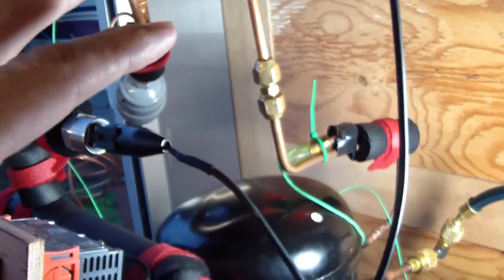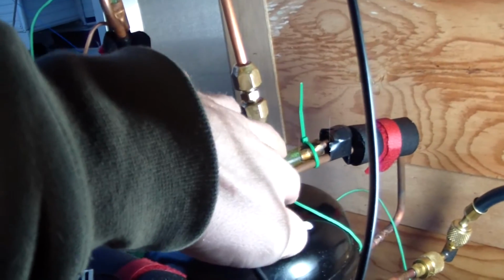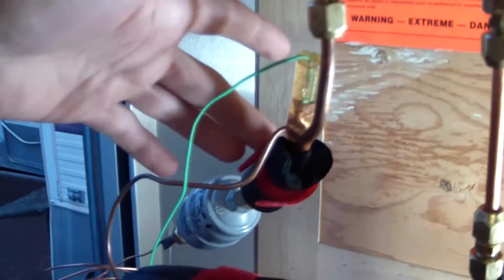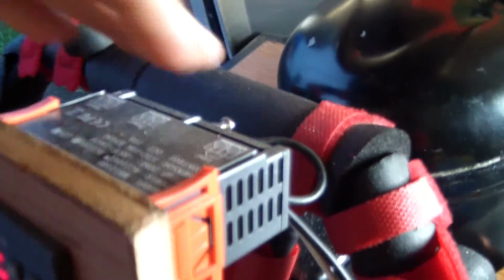There's a series of thermocouples throughout the system. Discharge superheat, very important. Then we have subcooling, important. We have one directly after the evaporator. I can't see it all that well, but it's up in there. And then we have a fourth important one, which is after the heat interchanger and the suction line, right before it goes into the compressor.